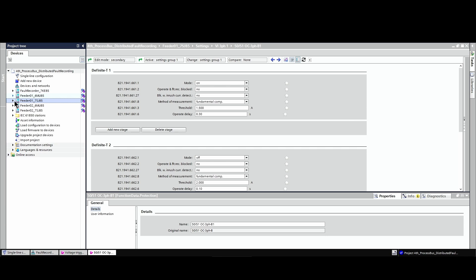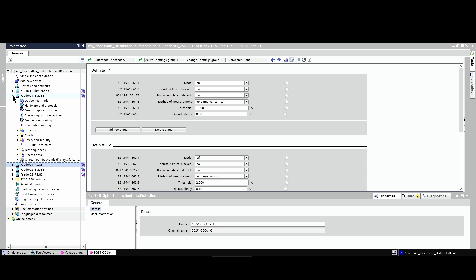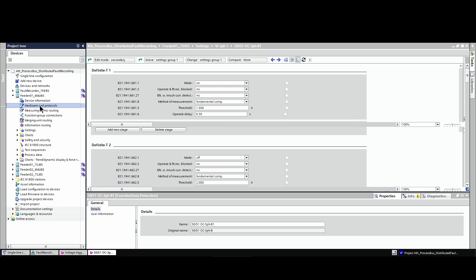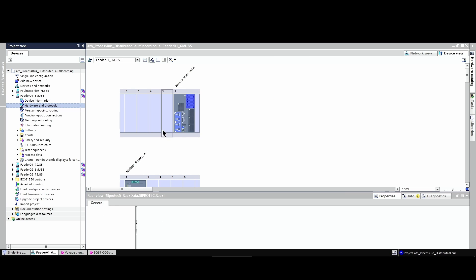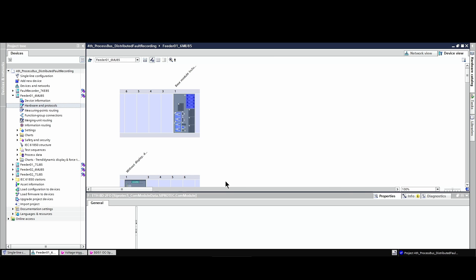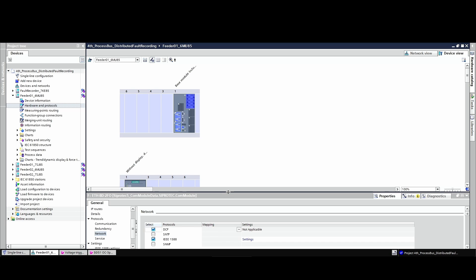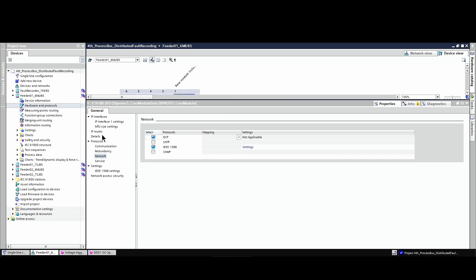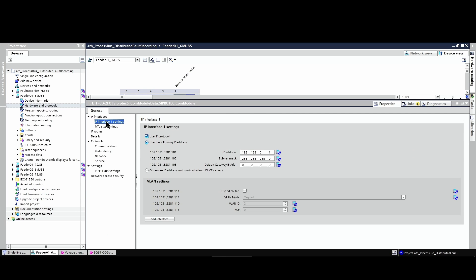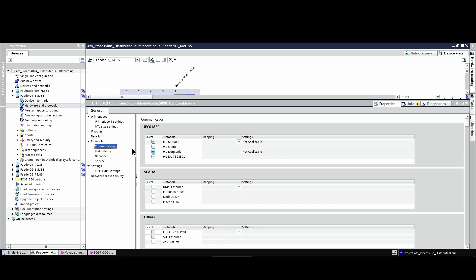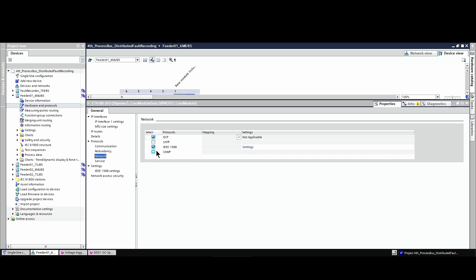In the merging unit, just above the protection relay, we click on hardware and protocols. We click inside the settings for the communication BD module. The settings are slightly different compared to the fault recorder. The IP addresses are assigned, and in the communication we can see that the merging unit is selected as a merging unit. Equally to the fault recorder, the time synchronization is IEEE 1588 precision time.